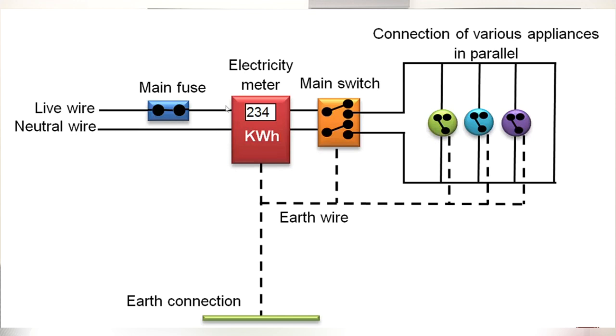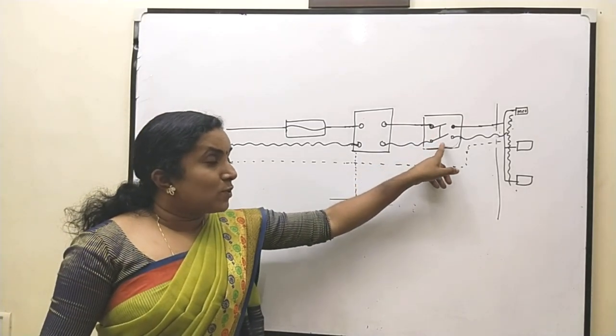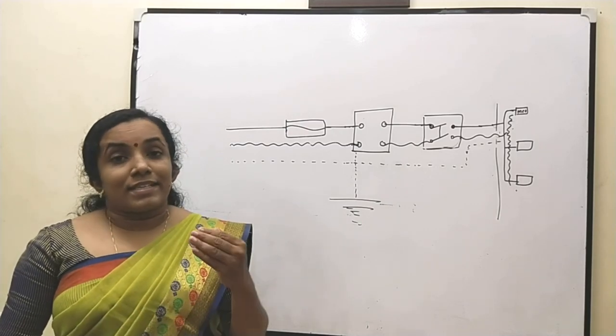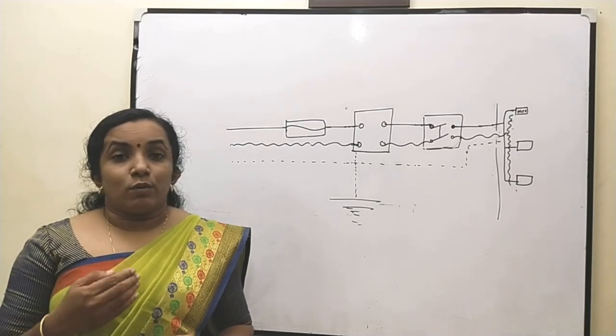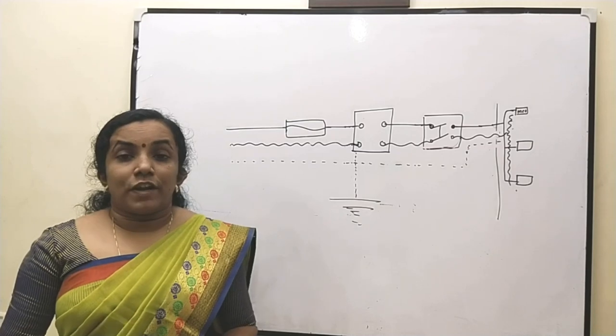After the company fuse, the cable is connected to a kilowatt-hour meter, usually mounted on the walls of the house. From the meter, connections are made to the main switch, which is a double pole switch. A double pole switch disconnects both the live and neutral wires simultaneously, providing extra safety during maintenance work in the house. From here, wires go to different parts of the house.